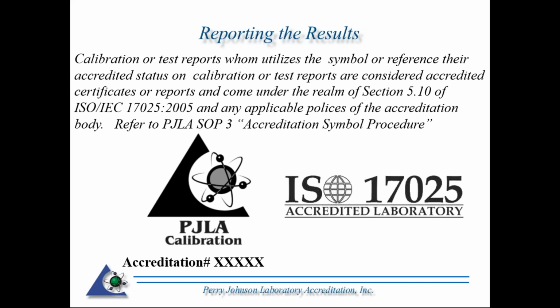For PJLA, I reference SOP3, our accreditation symbol procedure. This references requirements on top of 17025 when you utilize our symbol on your calibration and test reports. The example up there on the screen depicts how that needs to be shown.